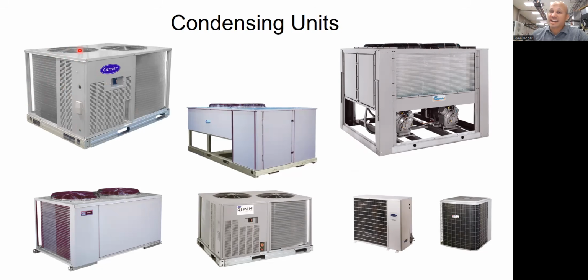The compressor would be located inside the building. So that would be a significantly different type of setup, but it might look similar. It would look something like this one right here in the middle, except you can't see the compressors in the back here, which is fine because now it looks like a condenser instead of a condensing unit. So condensing unit means it has the compressor also in it outside. Condenser means the compressor is inside.